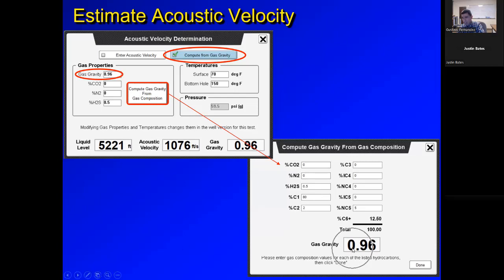So the software will use the gas gravity, and the pressure measured by the pressure transducer. If you don't have one, you can input that, but normally you have a pressure reading from the sensor, and you have a temperature input. So the software will basically look at the environment where this sound wave is traveling. What is the gas composition that it is traveling through? What is the gas pressure? And what is the gas temperature? So gas gravity, pressure, and temperature are the 3 factors that affect how fast the sound travels in that specific environment. That's not something you control. You can put more or less pressure to have more or less energy, but it's not going to make the sound travel faster. The sound travels at its speed based on the environment. We're just providing enough information to the software to calculate the resulting acoustic velocity.